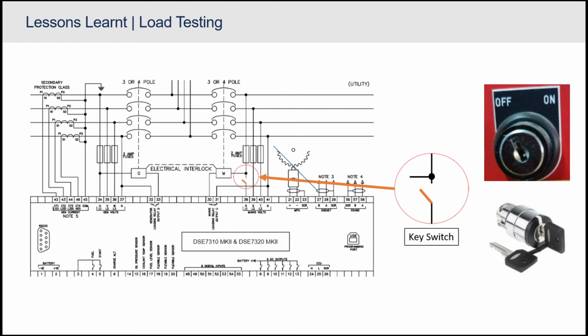So it's actually better to run it less frequently, let's say once a month, but under load. Quite often the procedure to do that isn't there, and secondly, people don't like handling the switchgear and isolators to switch that - it's quite terrifying, especially for me, I must admit. I'm a mechanical engineer, not electrical, so electricity scares me quite a bit.